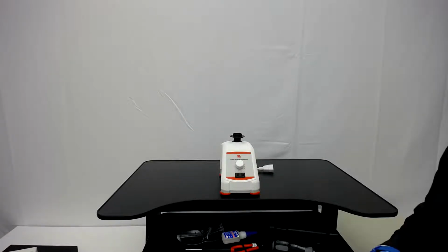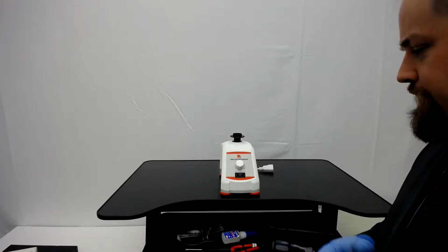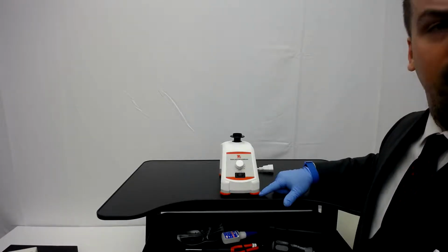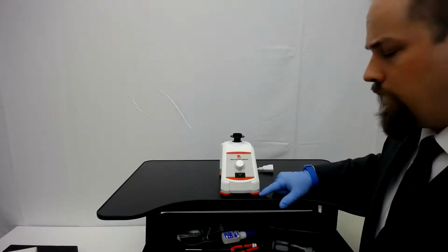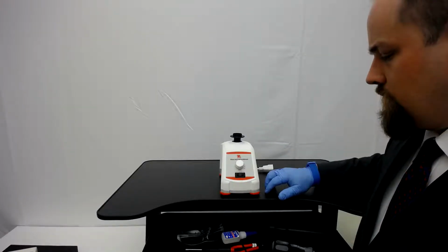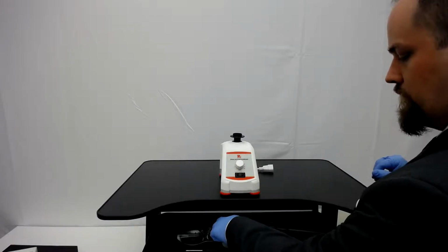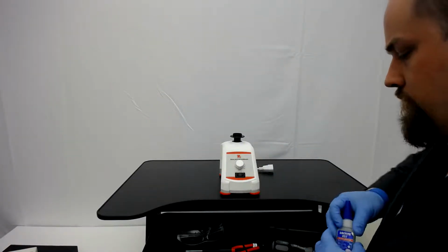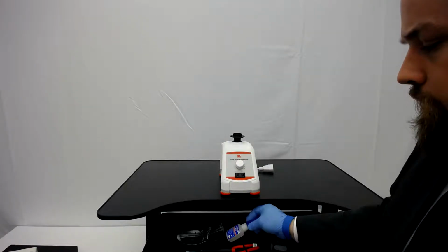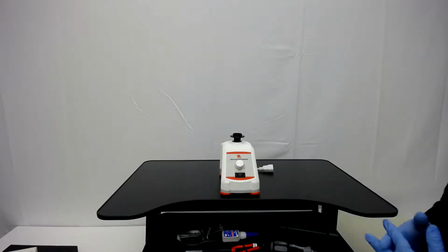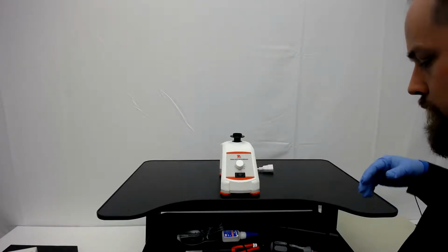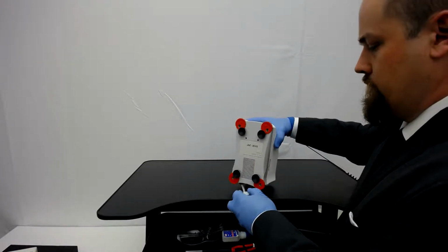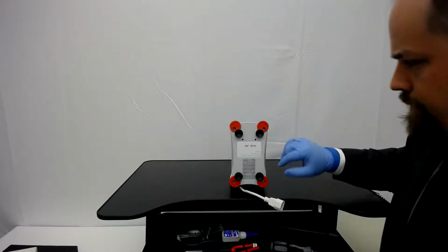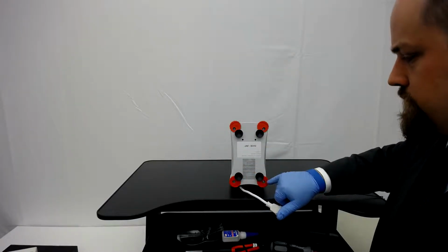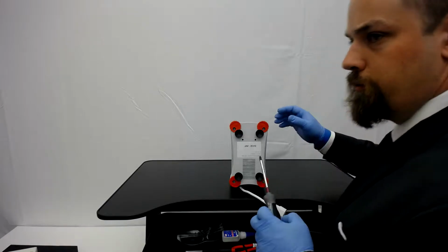Some other things we'll need. This will have a slight repair to these aesthetic red feet that are not on the hot plate stirrer. If one of these does pop off, we will be using Loctite 411 to adhere it back on. This is an instant adhesive. But primarily, this is very similar to what we did with the hot plate stirrer. All right, we're going to disassemble the unit. To do that, we're going to flip it up. And again, there's 4 screws on this unit that we remove.